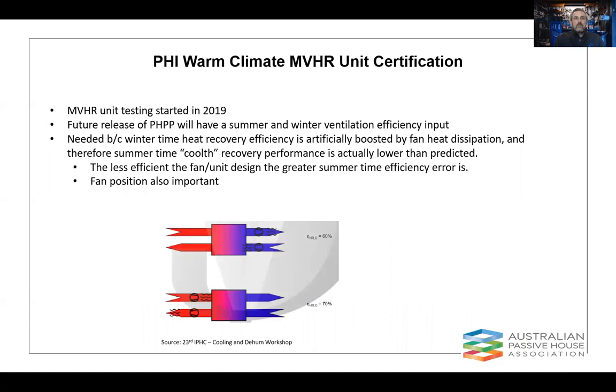So first of all, PHI warm climate unit certification. So most people are probably familiar with the certificates for MVHR units, and they cover things like airflow rates, they cover efficiency, they cover specific fan power consumption, a little bit on noise. And to date, they've really been tested for cool climates. So the standard test data has been something that's more typical of Europe or northern parts of Europe.